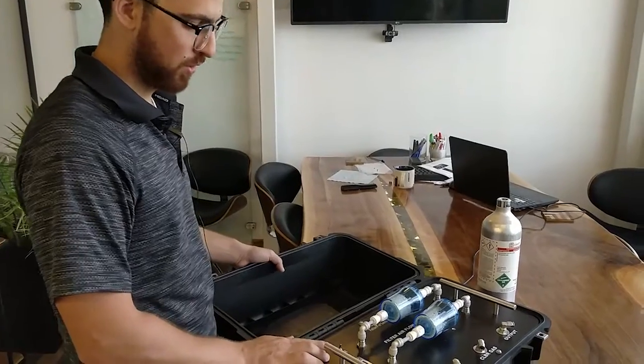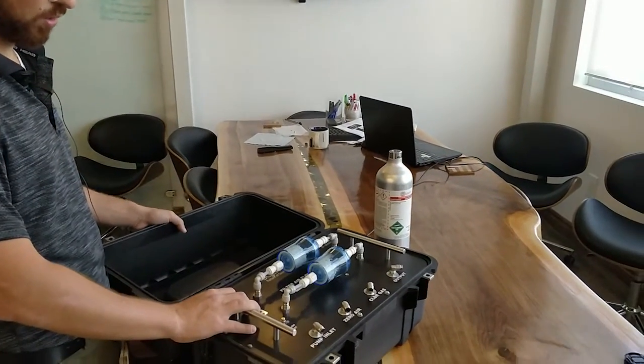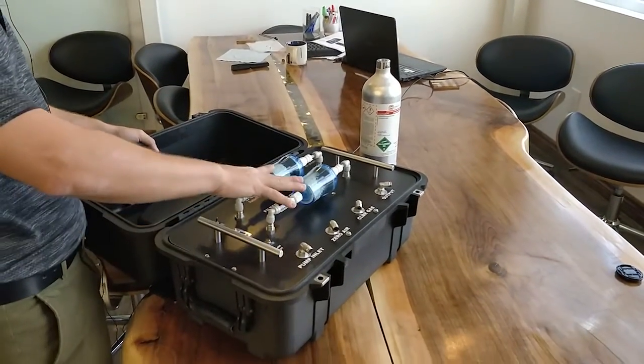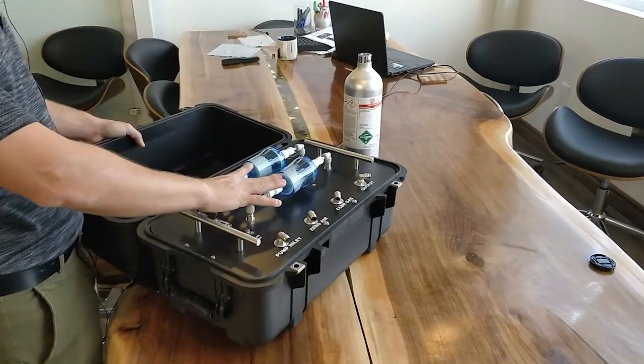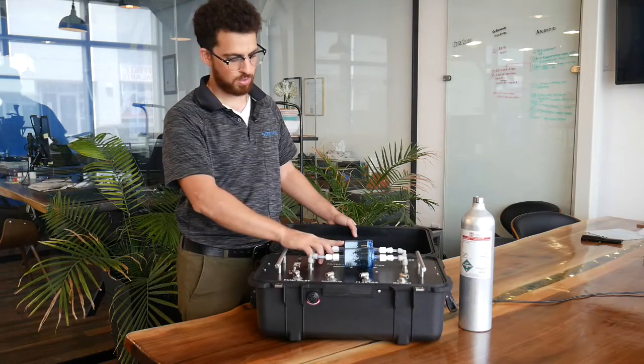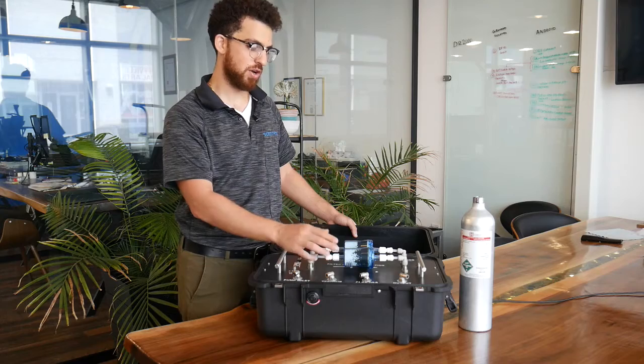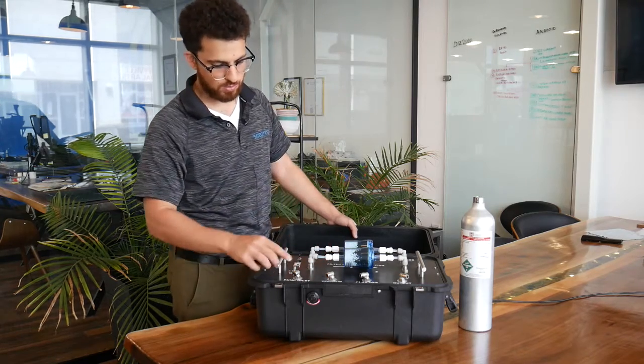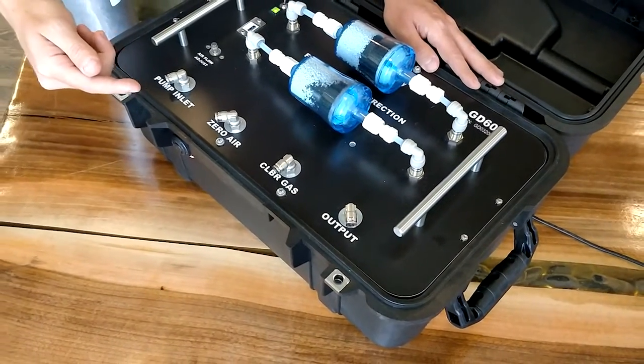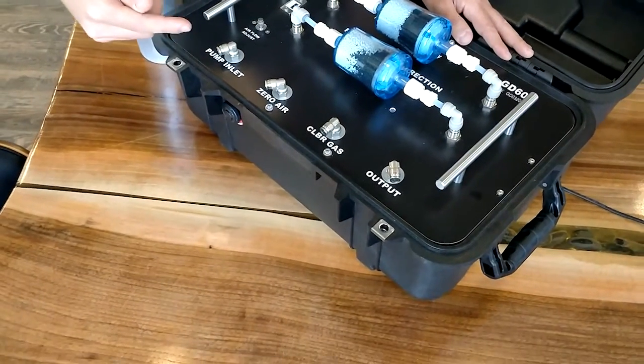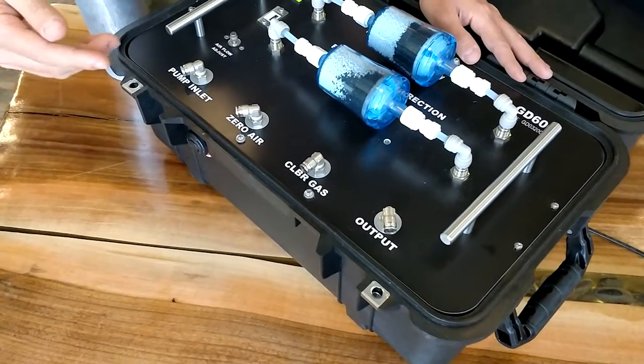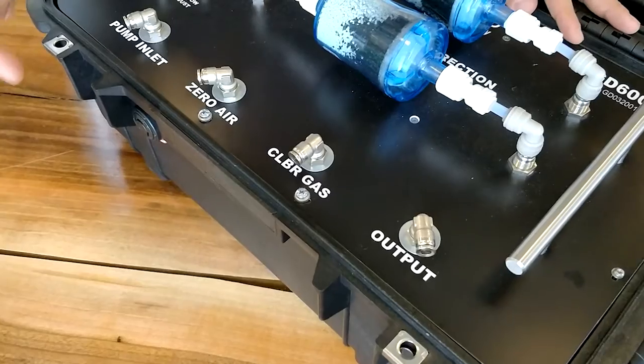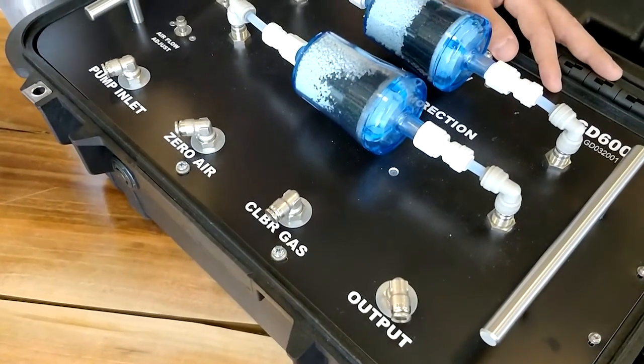Here is a power switch with an LED to indicate that the unit is on. These two are scrubbers. One is used for generating zero air, and the other one is used for cleaning the air as it exits the unit. Here is the pump inlet. The pump will pull in air from this port here. It'll be pulled in through here, scrubbed, and then mixed with your calibration gas, which goes in here.